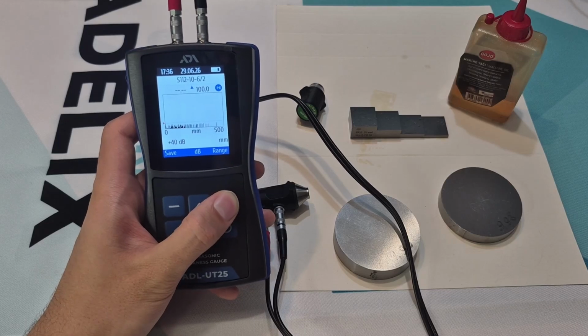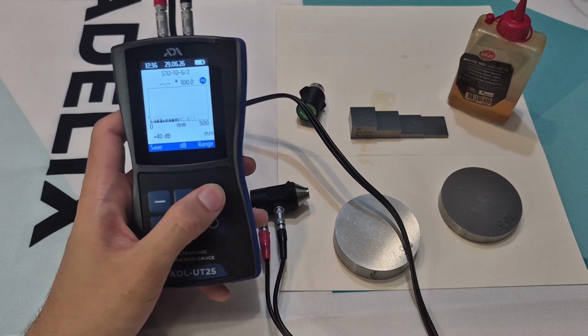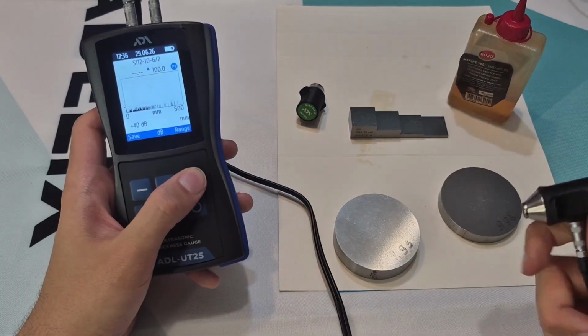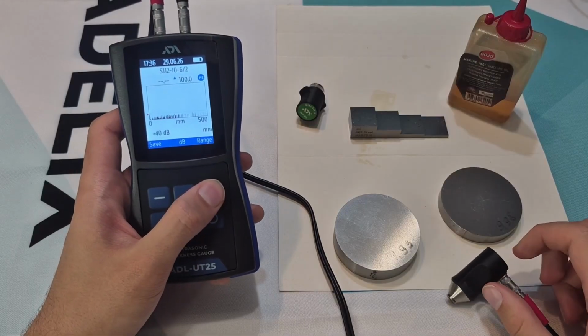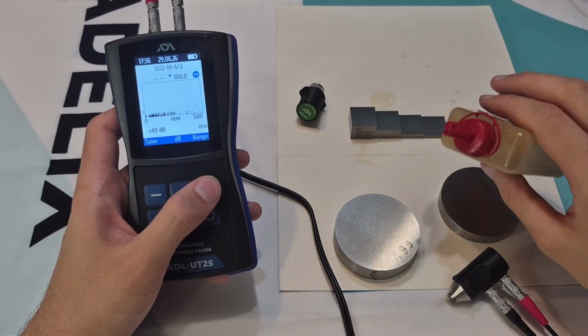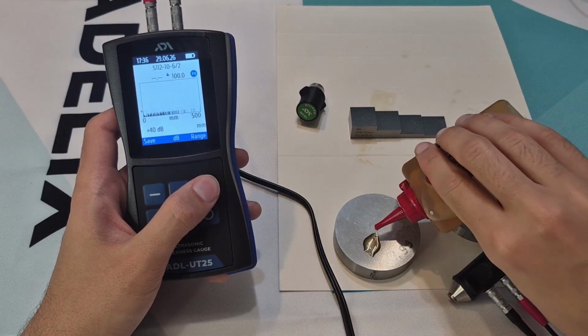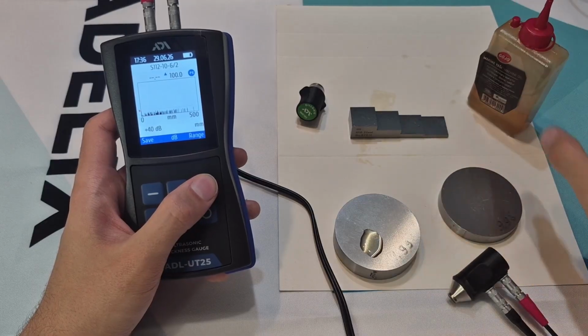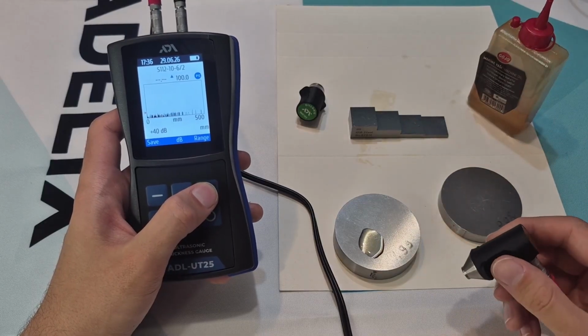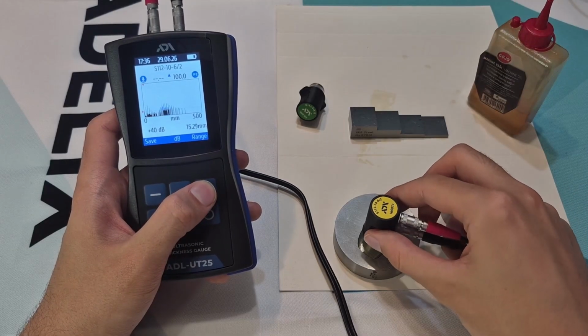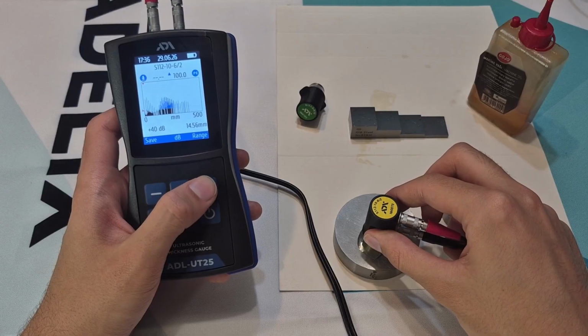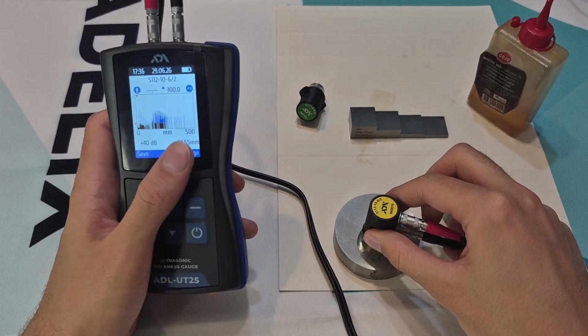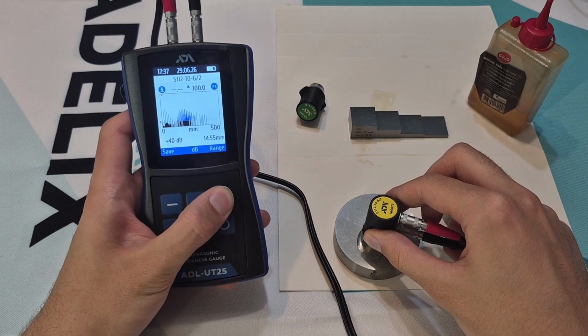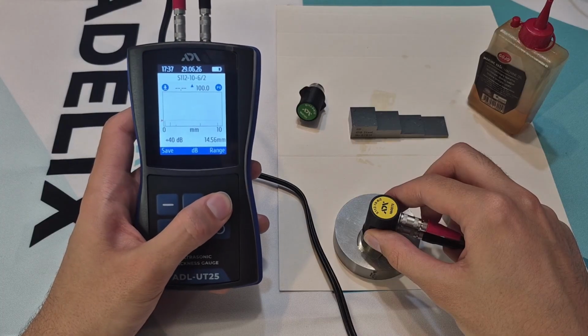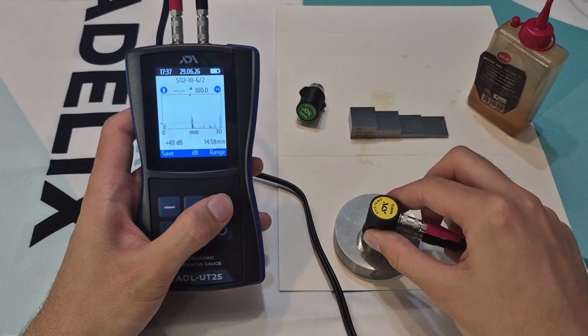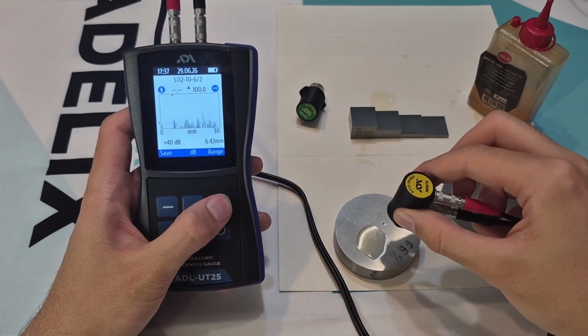Let us see how it works. We place the transducer on the sample. A measurement range from 0 to 500 millimeters is currently selected. It can be changed with the range button. The thickness of the sample is 15 millimeters. The reflected signal is shown on the screen, while the measured thickness is displayed at the top.